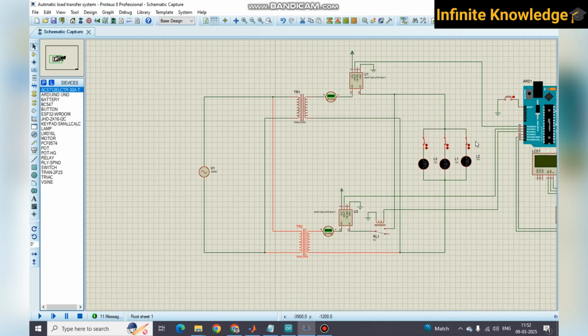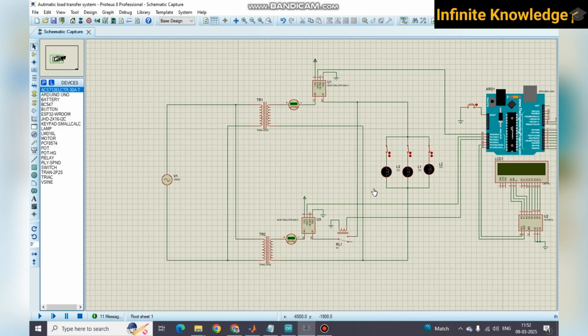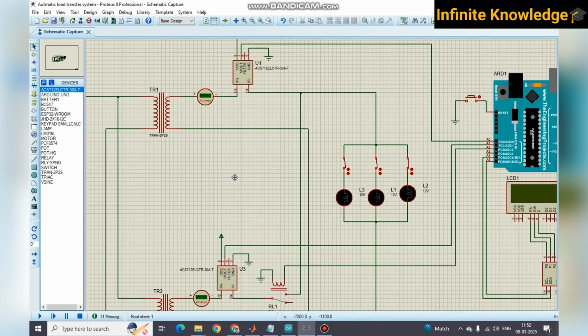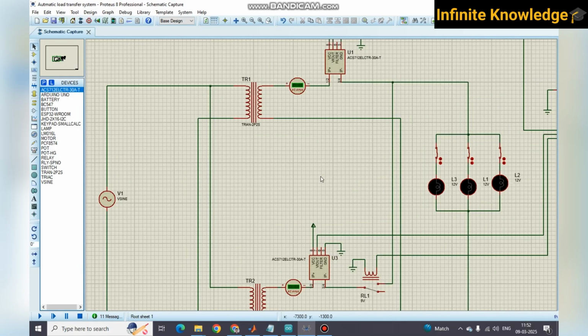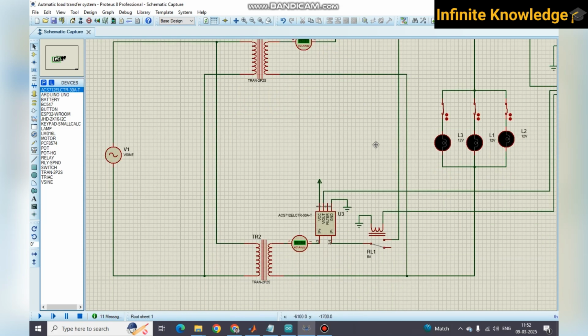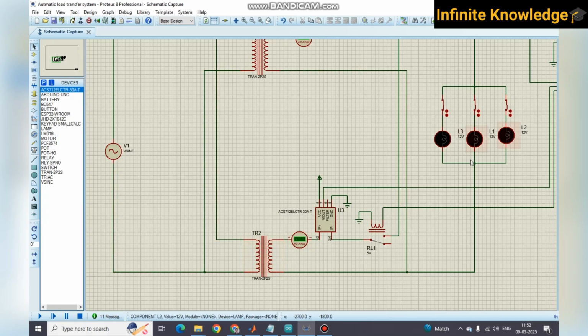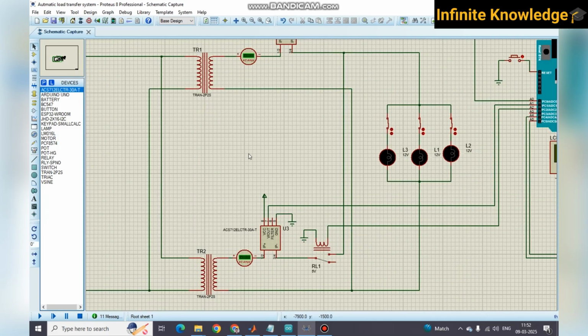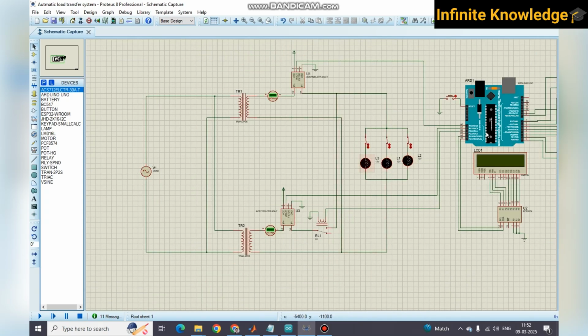If the load increases continuously, because nowadays grid expansion is happening and electricity consumption is increasing, one transformer is unable to feed all the load. In that situation, we connect another transformer in parallel to the first one. If the ampere increases for a particular high load condition, because the load is continuously fluctuating, and the load gets so high that the primary or master transformer, TR1, is unable to feed it, TR2 comes into the picture and goes in parallel with the primary one. Both transformers are on and feeding the load at the same time.